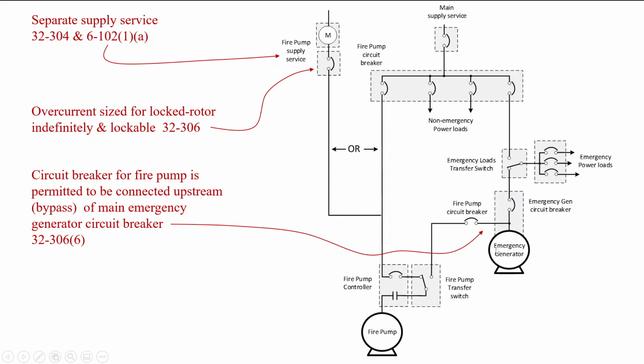The emergency generator would still be capable of supplying power for the fire pump because the fire pump circuit breaker is upstream or before this breaker. And so the redundancy is increased. There's a higher chance that the fire pump will continue operating even if there was a problem with some of the distribution of power to emergency power loads.